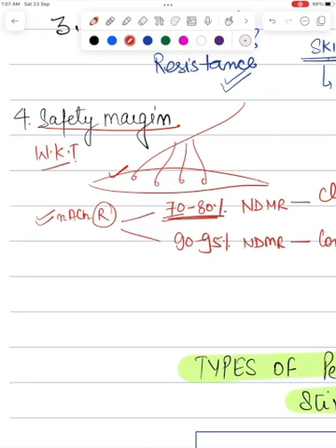Hence, currently available equipment allow insight only into this 70 to 95% range of receptor occupancy. That means that even if the device shows complete recovery, almost 70% of receptors could still have been occupied by non-depolarizing muscle relaxant but no longer detected with neuromuscular monitoring. So this just has to be kept in mind.